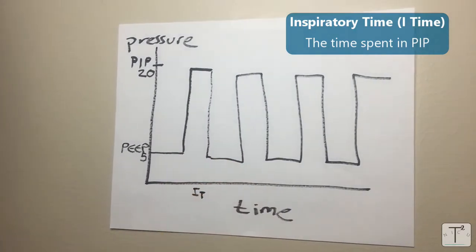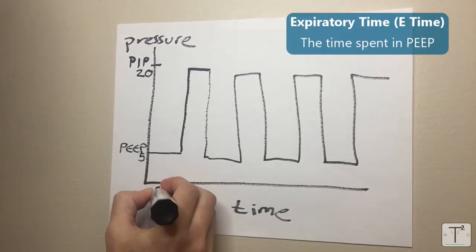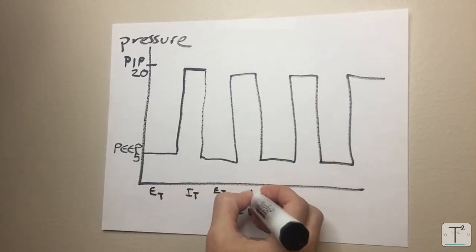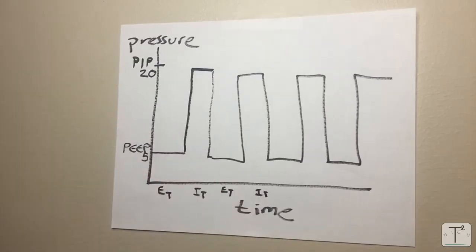The time spent in PIP is called the I time or the inspiratory time and the time spent in PEEP, although we don't use this as often, is called the E time. Here you see E time and then I time. One breath is equal to the E time plus the I time.